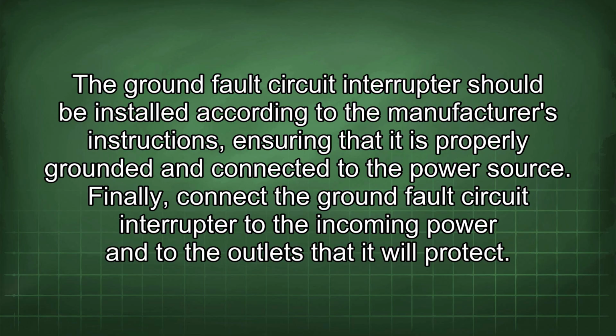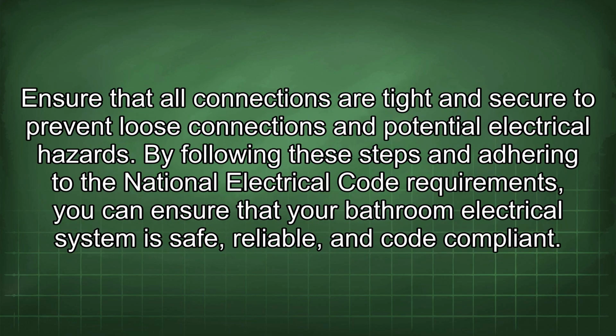The ground fault circuit interrupter should be installed according to the manufacturer's instructions, ensuring that it is properly grounded and connected to the power source. Finally, connect the ground fault circuit interrupter to the incoming power and to the outlets that it will protect. Ensure that all connections are tight and secure to prevent loose connections and potential electrical hazards. By following these steps and adhering to the National Electrical Code requirements, you can ensure that your bathroom electrical system is safe, reliable, and code compliant.